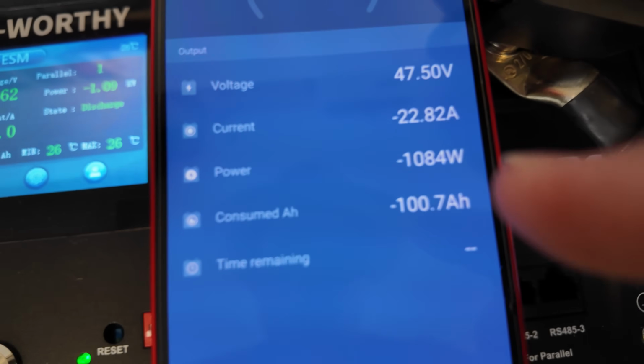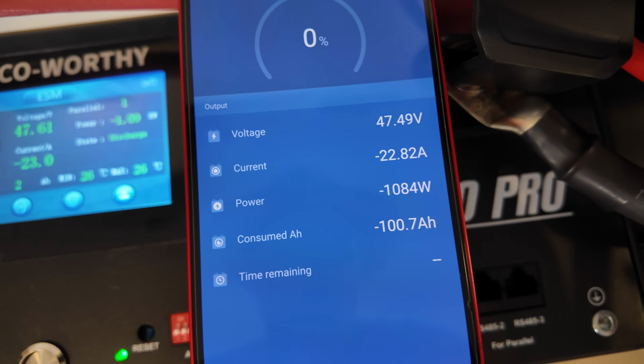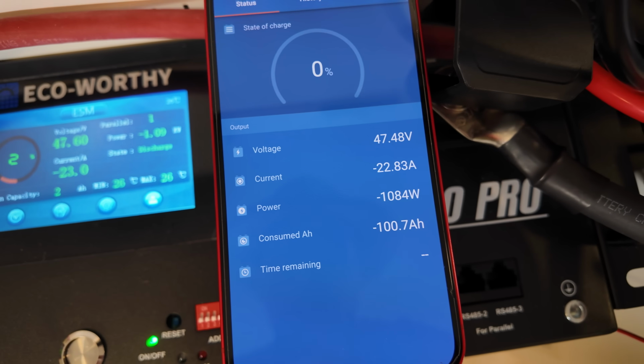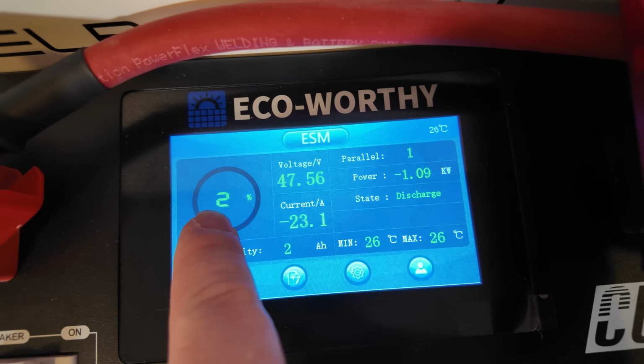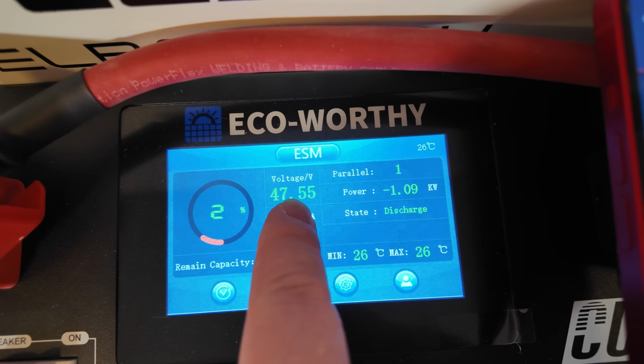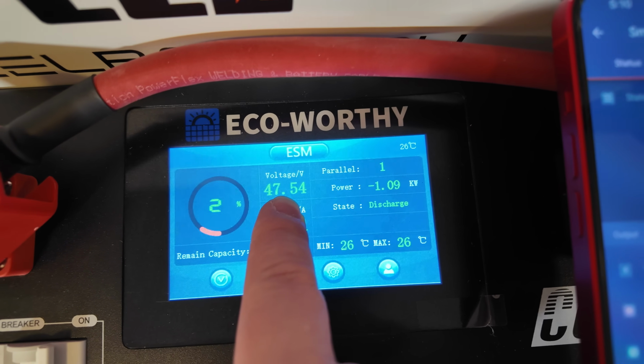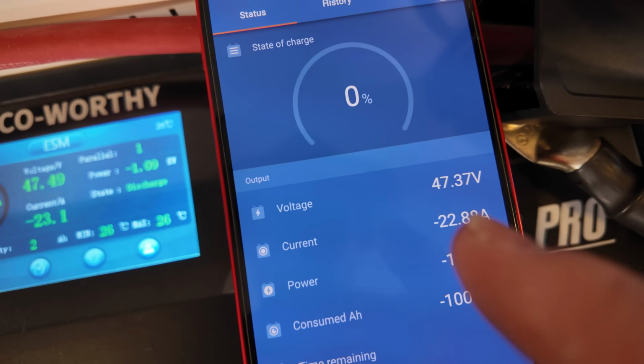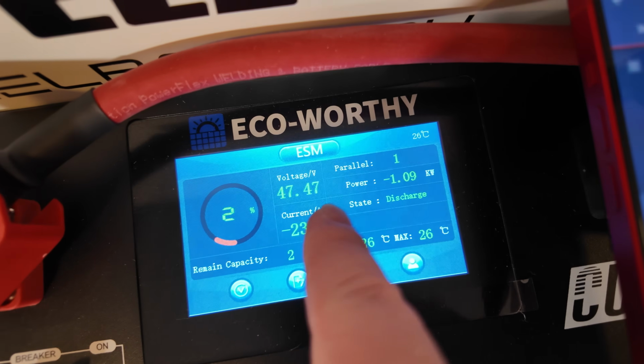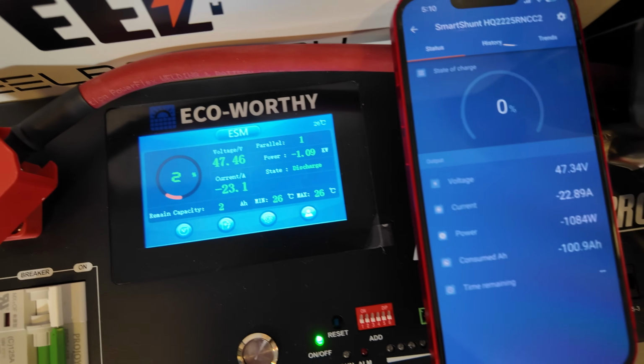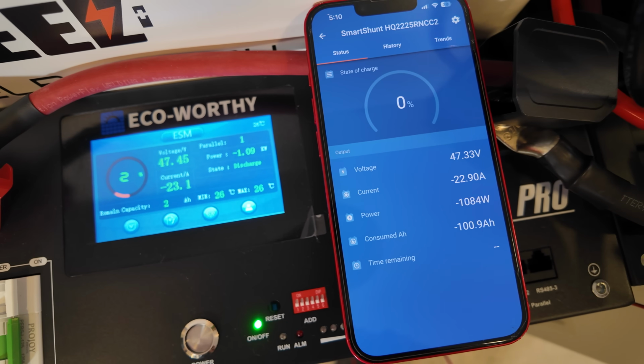Just want to give you a quick update on this capacity test. If you look right here on the Smart Shunt, 100.7 amp hours, so it has pulled full capacity and then some. According to this screen, we've still got 2% left. We're coming down the home stretch because we're at 47.5 volts. The shunt is recording 47.3. Now we're down to 0.4. Anyway, voltage is dropping. We'll let this run a little longer and see where it cuts out.